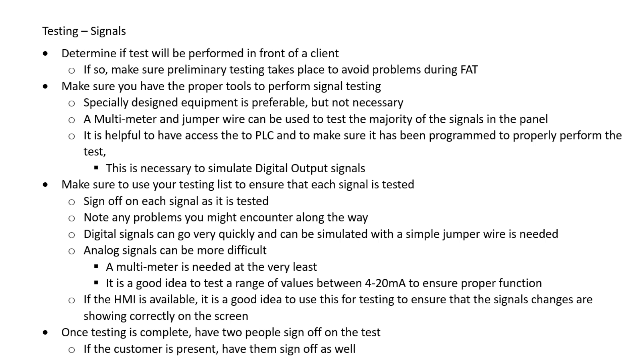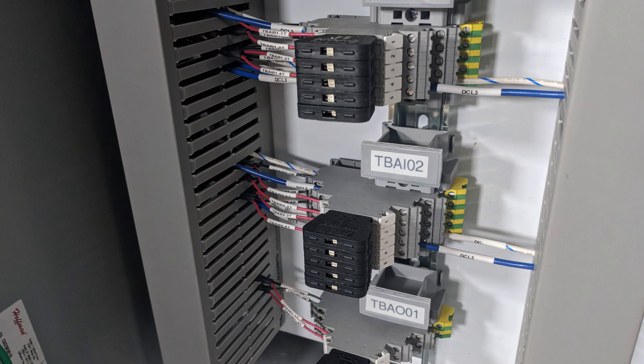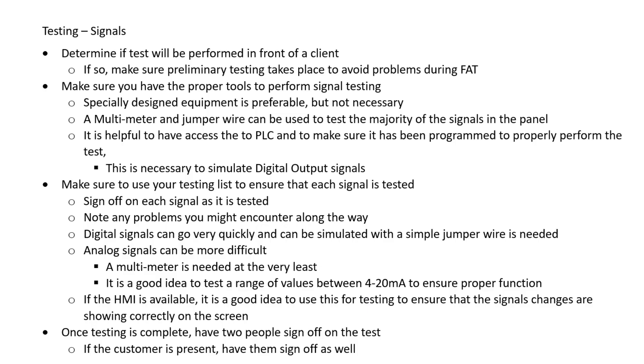With analog signals, there's a little bit more to it. At the very least, you need a multimeter, because we want to be able to measure milliamps — we're typically measuring between 4 to 20 milliamps on an analog signal. Without a multimeter, we don't have the ability to simulate that 4 to 20 milliamp signal. In most cases you'll want something more like a process meter that can perform that type of 4 to 20 milliamp simulation if you don't have access to specialty equipment designed for that function.